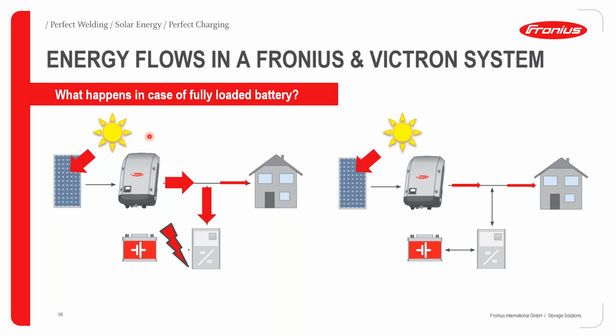So in this particular example, we can see that the Fronius inverter is still generating nearly 100% of what is coming from the DC side on the solar panels. Most of that has been going to recharging the batteries, but a bit of that has been going to load consumption. If the batteries are fully charged, this configuration does not need a hardwire connection between the inverter charger and the Fronius inverter for regulation. So there will be frequency shifting, where the Victron inverter charger is going to increase the frequency gradually up to a point whereby the output of the Fronius inverter will be nearly zero.